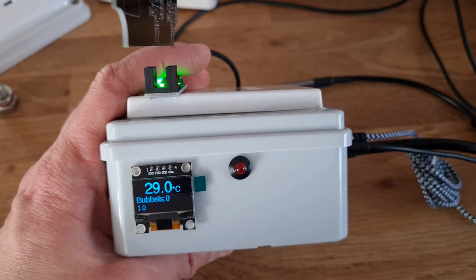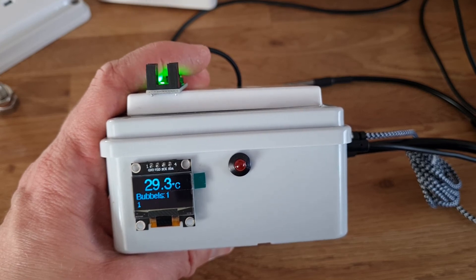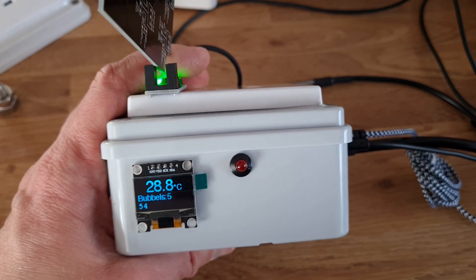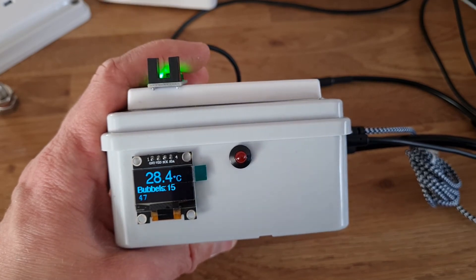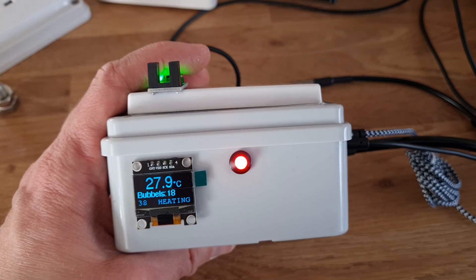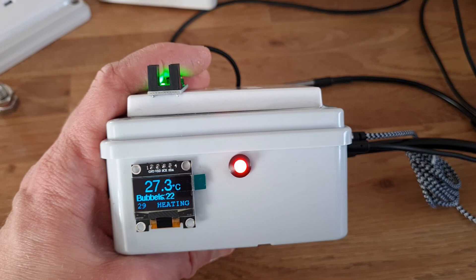With bubbles — I'm going to put this in the way of the light so it can detect it. One bubble. I'm holding it there and it still says one bubble. Remove it — still one. Let's wait for it to finish uploading. Two. Three. And if you do it really quickly, it's only doing a quarter of a second. The one thing it does is while it's uploading, it is still counting bubbles and still adjusting the temperature — it will not fault. It still works in the background.